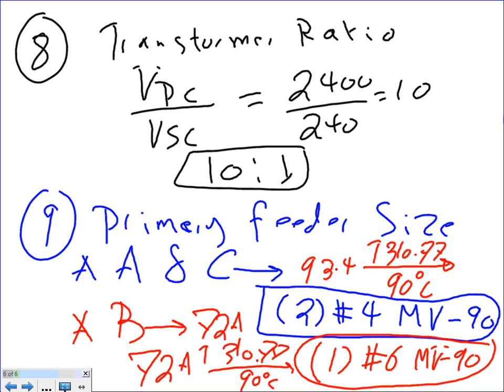So that's an assumption. Now why would I use this one? This is the most common one for medium voltage, though if this applies to you, you might have to use a different one. Why did I use it? One circuit - this is pure parallel. If we were parallel, we'd go 3 circuits, or up to 6 circuits. But we only have 1 circuit, so we don't have to worry about it.